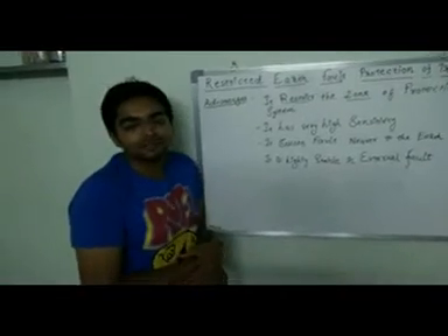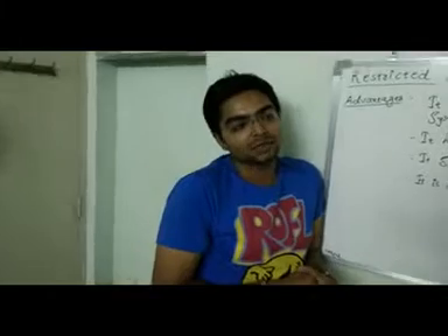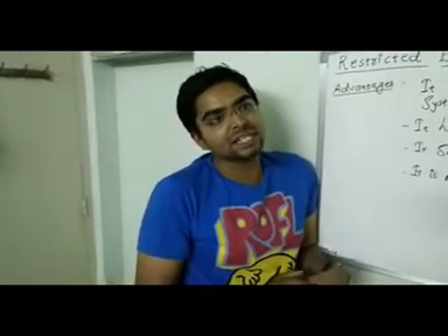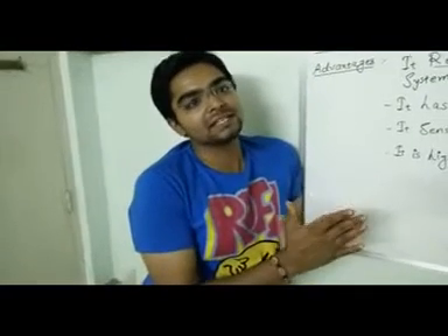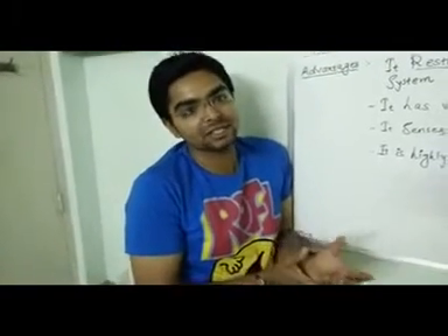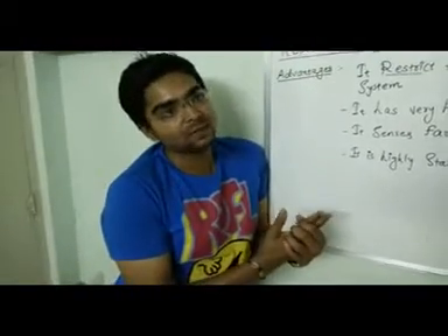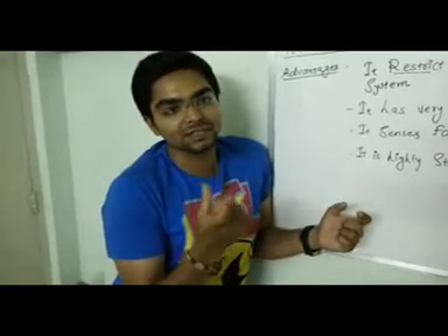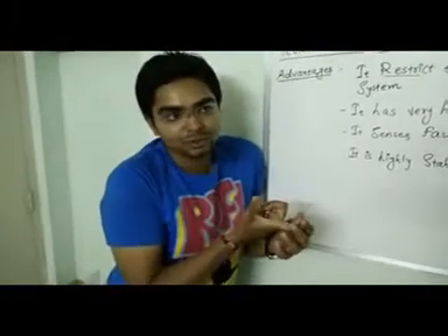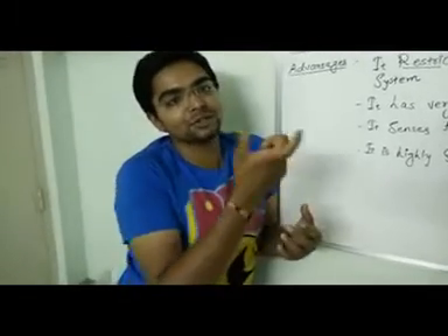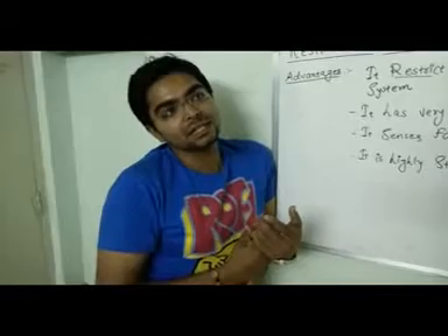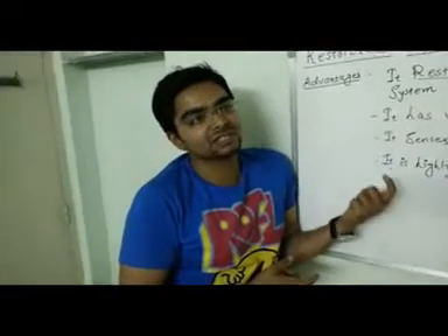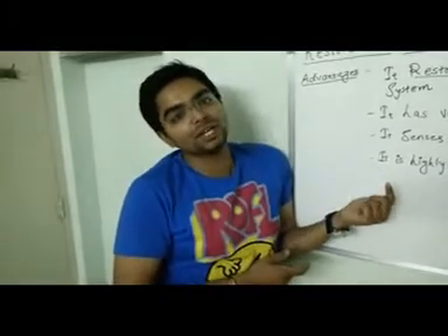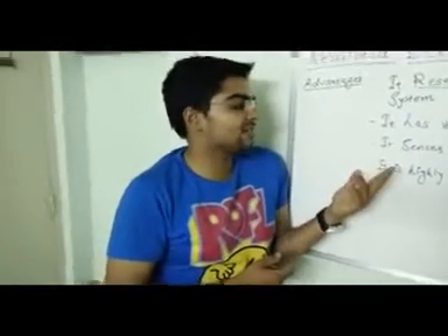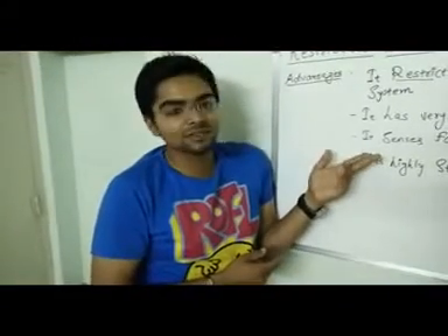Let's take the differential protection. In the differential protection, 20% of the winding is biased. That means if there is a fault in that 20% of the area, it won't be detected by differential protection. But with the help of this system, we can even detect that 20%. And as we know, a fault near to the earth is very hard to detect. So this system is so sensitive that it will even detect the fault near to the earth. That's why it's highly sensitive.